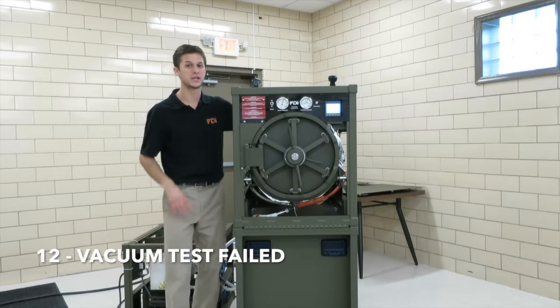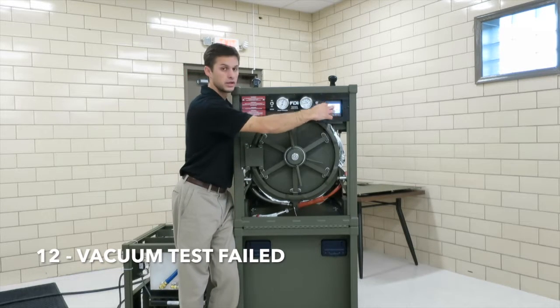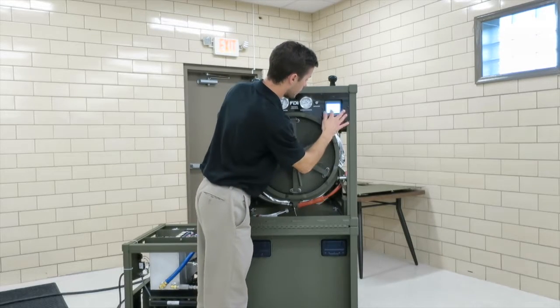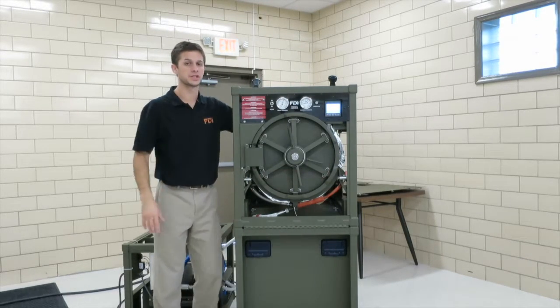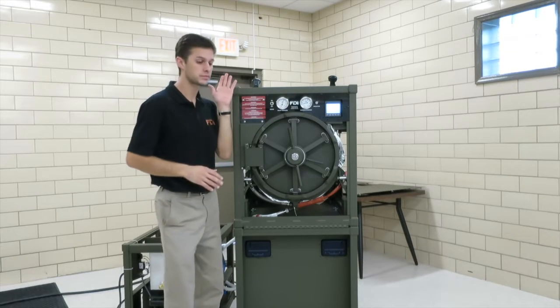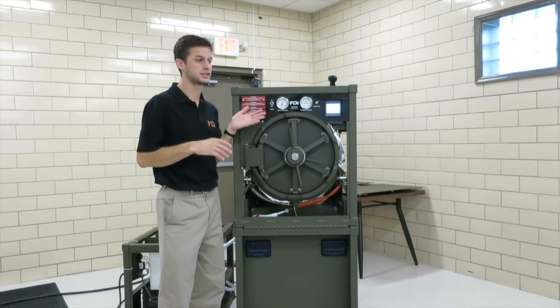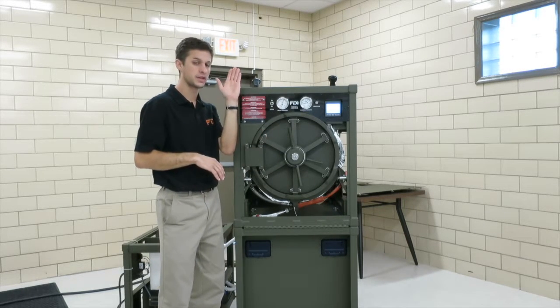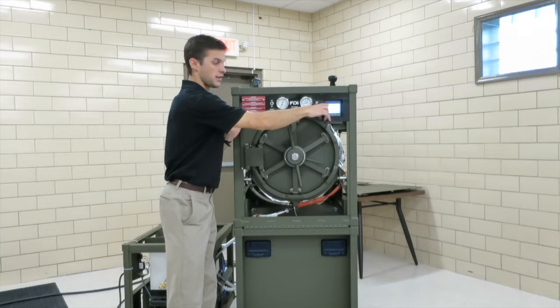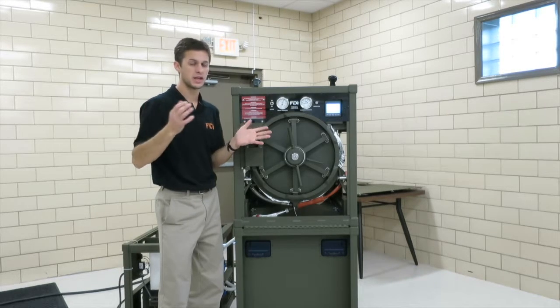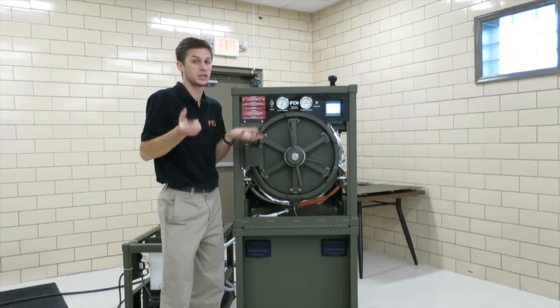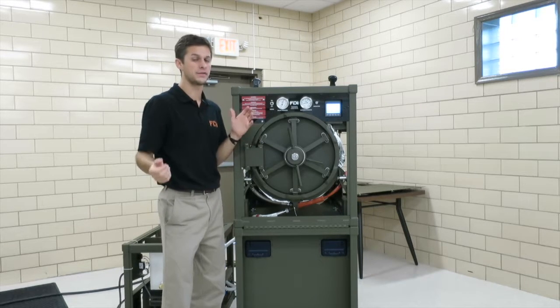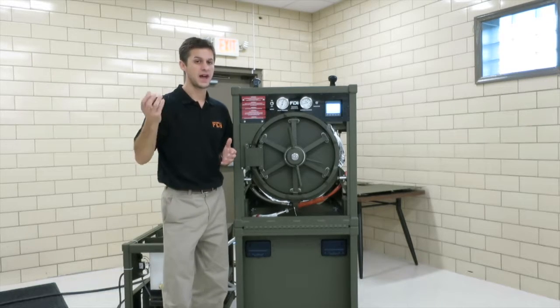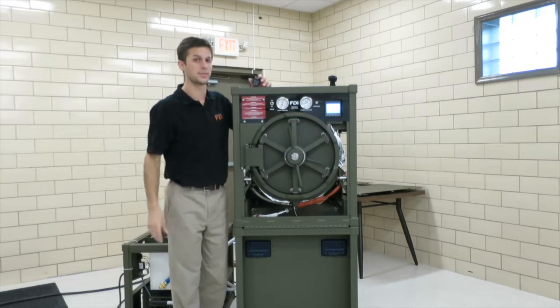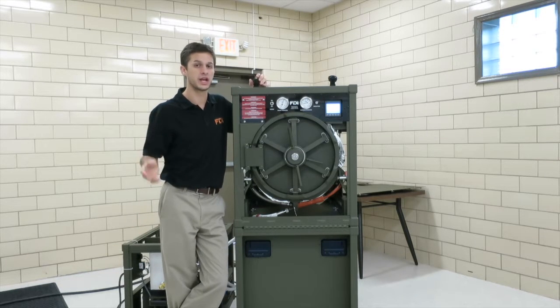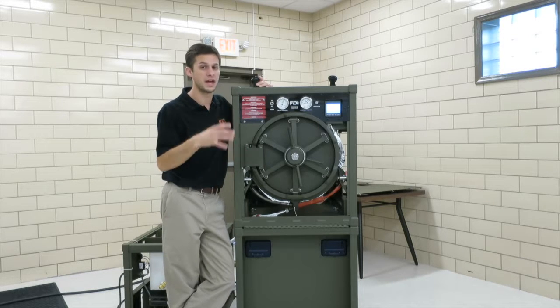Number 12 is vacuum test fail. The only time you'll get this alarm is if you've been running a vacuum leak test. If you're on the main menu and you're going to test and running a vacuum leak test, we have a video on vacuum leak test, but it's a 15-minute test. After the chamber stabilizes, the PLC records the value of vacuum in the chamber and waits for 15 minutes. If any leaks occur, it's going to let some air in, it's going to lose vacuum, and the final value is going to be a lower vacuum than the first value at the start of the 15 minutes. If that happens, you're going to fail your vacuum leak test, and you'll get a number 12 alarm. And there is a troubleshooting guide in the back of the manual to help you find that vacuum leak.